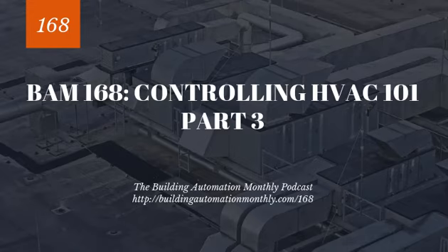When you're dealing with air-cooled chillers, and this will be true for all chillers, when you're enabling a system, just like with dampers on air handlers, you first have to make sure there's a path for flow. The worst thing you can do with a chiller is enable it and have no water flow.